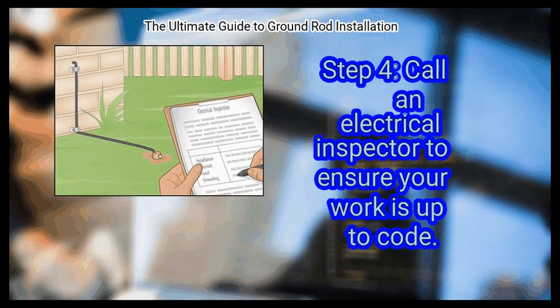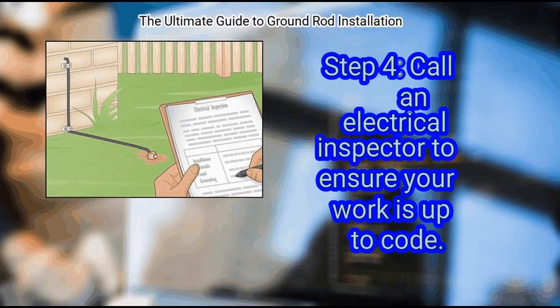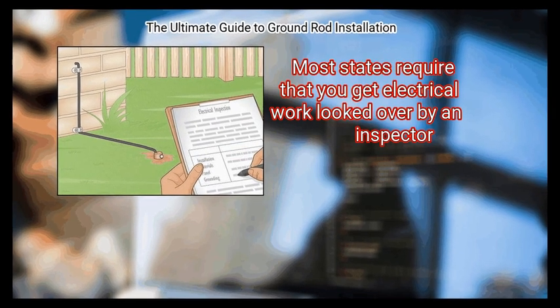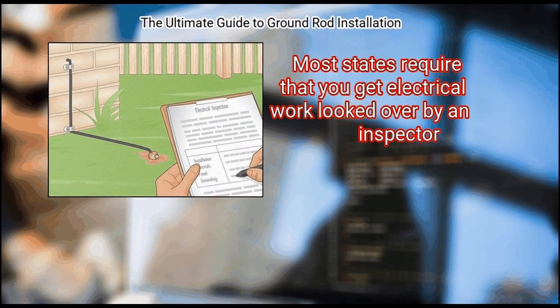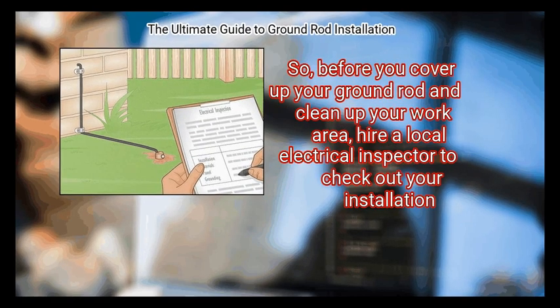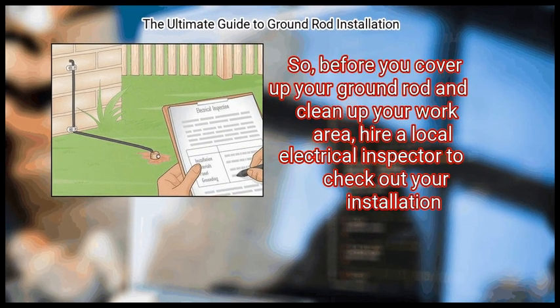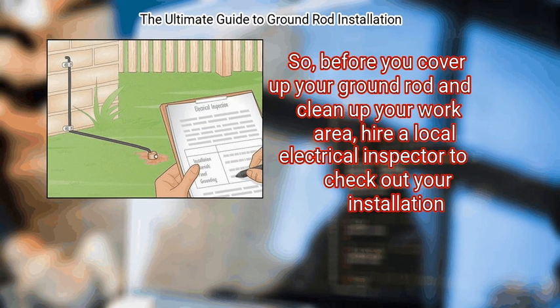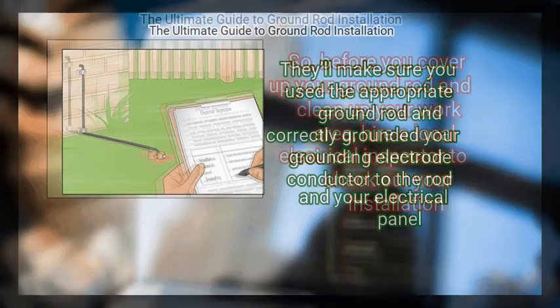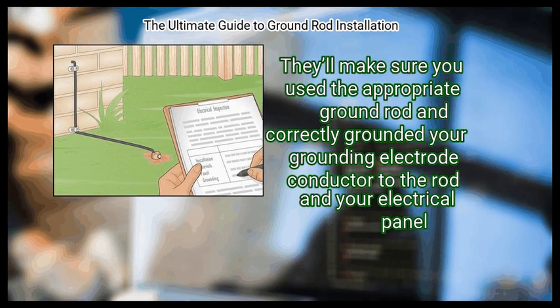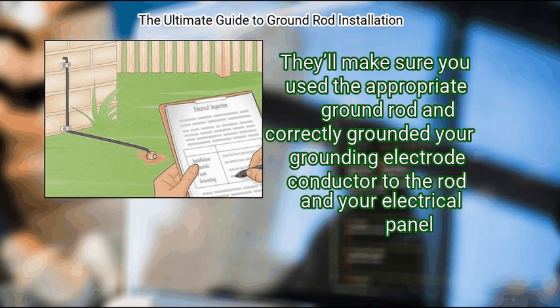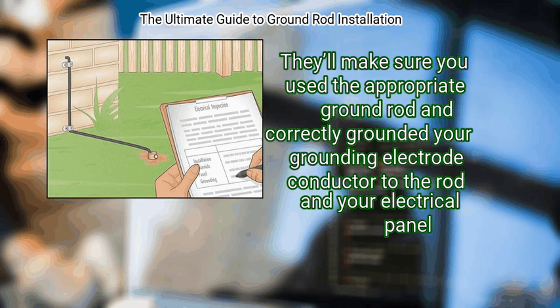Finally, call an electrical inspector to ensure your work is up to code. Most states require that you get electrical work looked over by an inspector. So, before you cover up your ground rod and clean up your work area, hire a local electrical inspector to check out your installation. They'll make sure you used the appropriate ground rod and correctly grounded your grounding electrode conductor to the rod and your electrical panel.